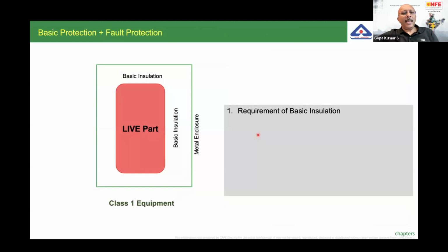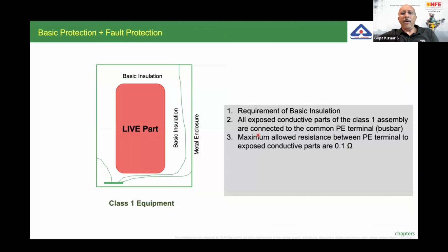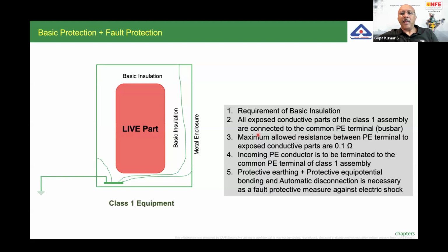Similarly, in a class 1 equipment, example live part, you have the basic insulation, you have the metal enclosure. The requirement of basic insulation is very well defined in the standard. The manufacturer is supposed to connect all the exposed conductive parts to a common PE terminal. Now, the maximum allowed resistance between the PE terminal and the body of the equipment is 0.1 ohm. The external, incoming PE conductor has to be terminated to the PE terminal. Protective earthing and protective equipotential bonding and automatic disconnection of supply as a fault protective measure against electric shock must be applied in the installation.